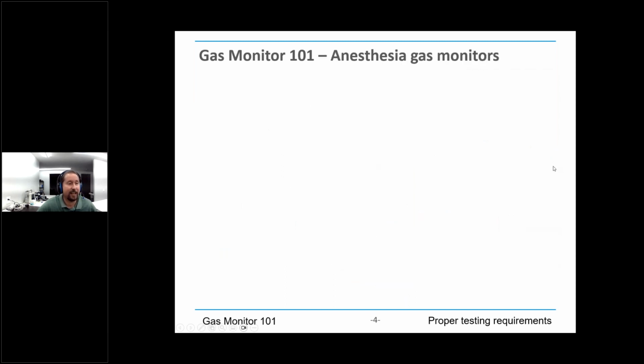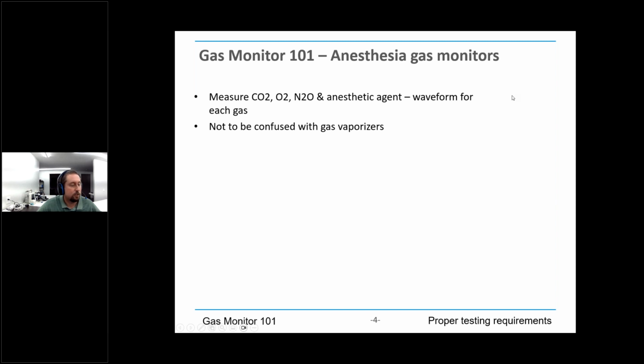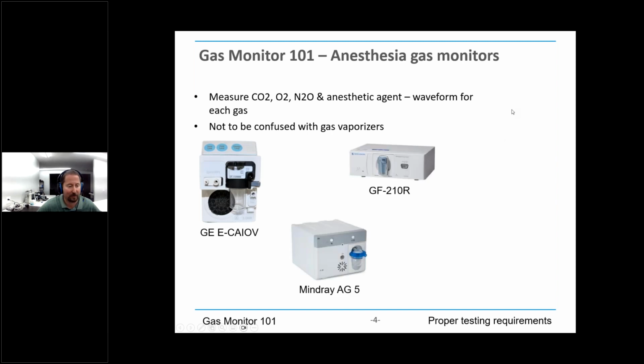There's a subset of gas monitors, which are the anesthesia gas monitors. These are like their other brothers. They measure CO2, but they also measure oxygen, nitrous oxide, which is laughing gas, and the anesthetic agent, and they all produce a waveform of those gases. And so they're just more complicated gas monitors, but they have PMs just like a regular capnometer. Don't confuse these with gas vaporizers. Those are the devices that take the liquid anesthetic agent and vaporize it and deliver it to the patient. A gas monitor is actually taking a sample from the patient and measuring how much gas there is in that sample. Here's some, again, examples that you're probably familiar with.